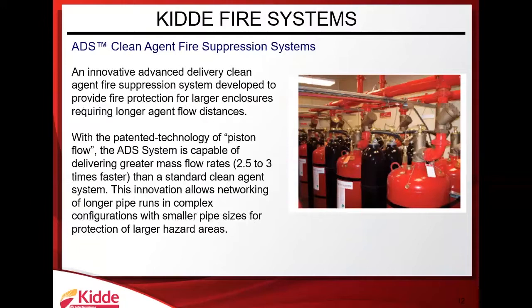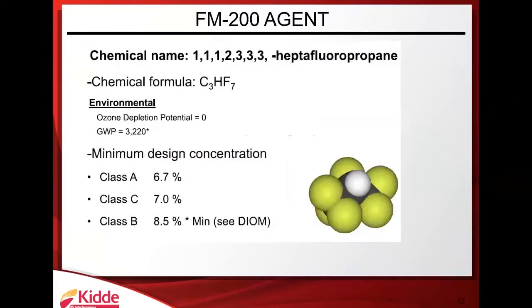It's pretty much the same as the previous one, but for applications where we need an even more rapid response or a larger hazard area, we're going to complement the agent and the cylinder with nitrogen, so that nitrogen can actually act as a piston and make the discharge a lot faster. The FM200 agent is the first one we're going to be looking at.